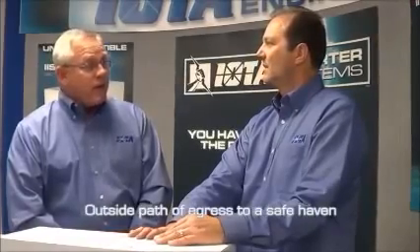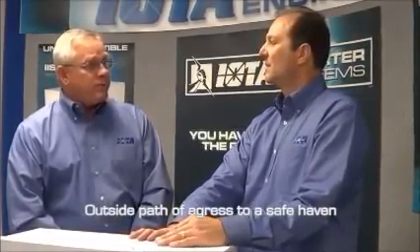And once the occupant gets outside of the building, are there any requirements? Absolutely. You're still required to provide emergency illumination outside the building to a safe haven. And are there any requirements in the code for testing and making sure that it's properly maintained? Absolutely. Every 30 days, you're to provide a 30-second test. In addition to that, a full 90-minute discharge once per year.